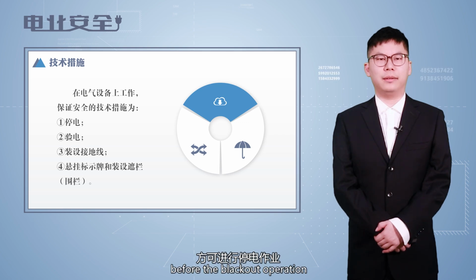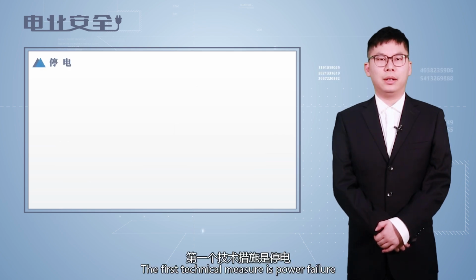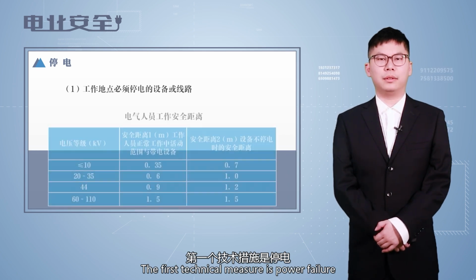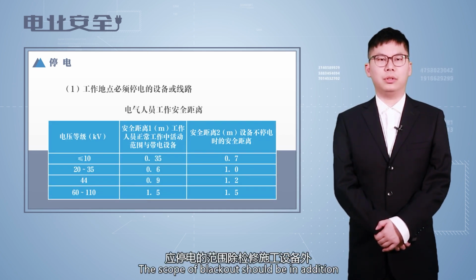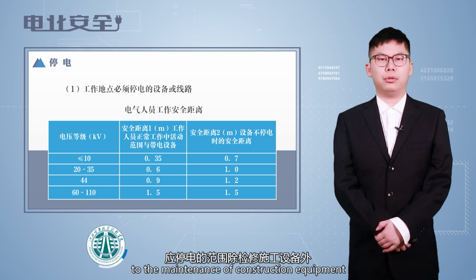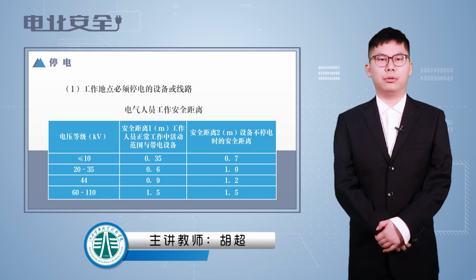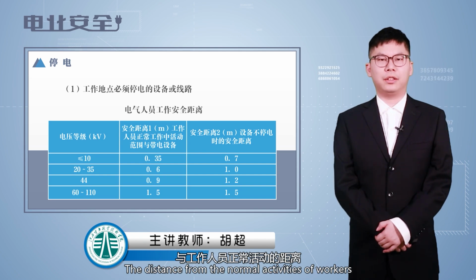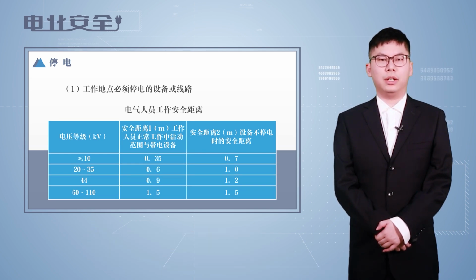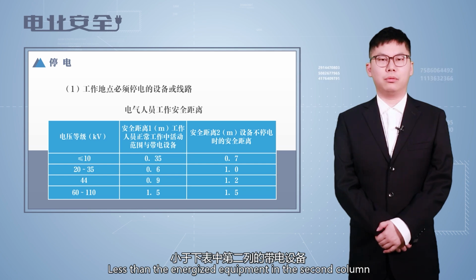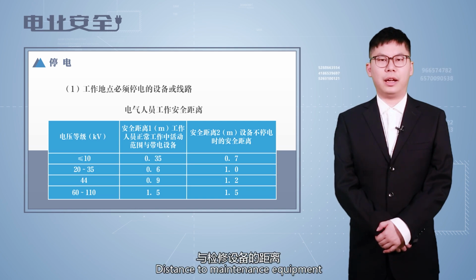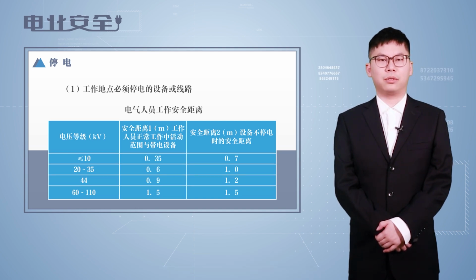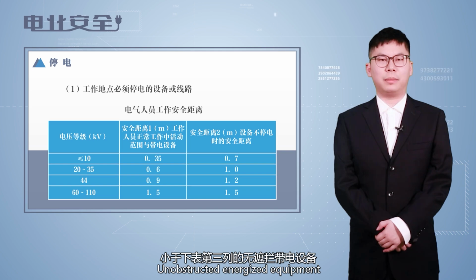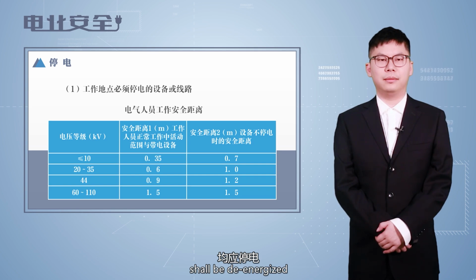But before the blackout operation, the first technical measure is power failure. The scope of blackout should be, in addition to the maintenance of construction equipment, the distance from the normal activities of workers less than the energized equipment in the second column of the following table, and distance to maintenance equipment, unobstructed energized equipment less than the third column in the table below, should be de-energized.